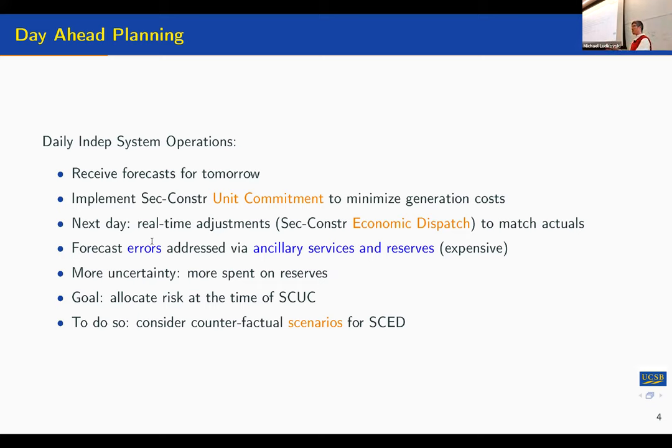Of course, you have to decide which of the possible units, which can produce up to 60 gigawatts, will be committed tomorrow. Those decisions are made on an hourly scale, so 24 hours for tomorrow. If you have a coal plant, you cannot just run it for 3 hours of the day; that's not physically possible. If you commit a coal plant or a gas generator, it has to be for multiple hours. That's why it's complicated to make a full plan for the next 24 hours, respecting all the network constraints, like congestion. This is a large scale optimization problem, something like 100,000 variables. That's the unit commitment.